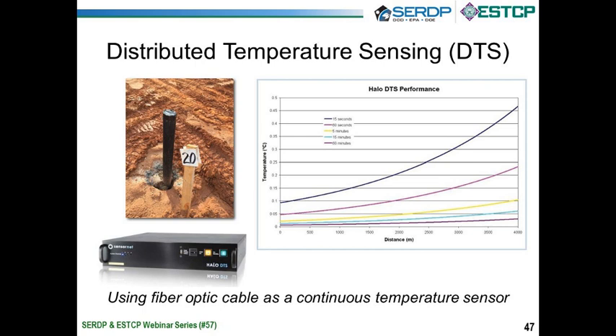But DTS operates on two primary principles, optical time domain reflectometry and optical frequency domain reflectometry, which basically means the speed of light is a constant, and also all atoms vibrate at a certain frequency when they're above absolute zero. So we shoot a beam of light down this fiber. It strikes the wall of the fiber and bounces back, and we time how long it took that light pulse to come back, and we also look at the frequency shift, and we can literally know the temperature of the glass fiber, which in this case is fiber inside that black pipe down to 225 feet. Maybe a little hard to read that graph, but we don't need temperatures but every hour or so.